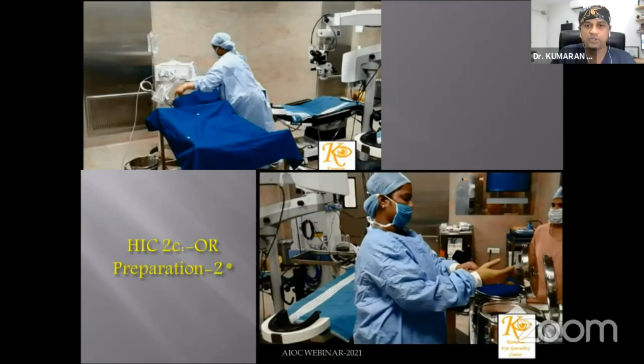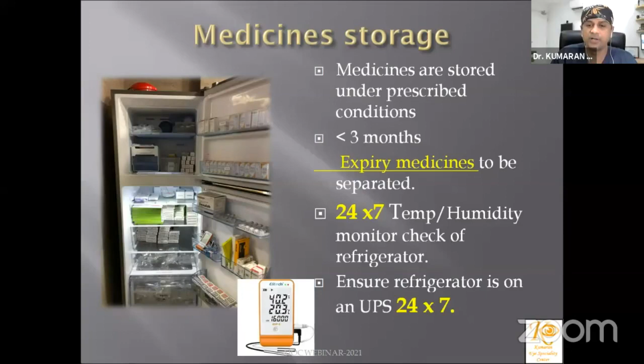An important point to mention about medicine storage is that all the medicine should be stored as per the manufacturer guidelines, and all the refrigerated medicines should be stored at the particular temperature, with temperature and humidity continuously monitored. It is also important that you put in a data logger, which is very easily available now, so that you will be able to record the variations in temperature on a daily basis.